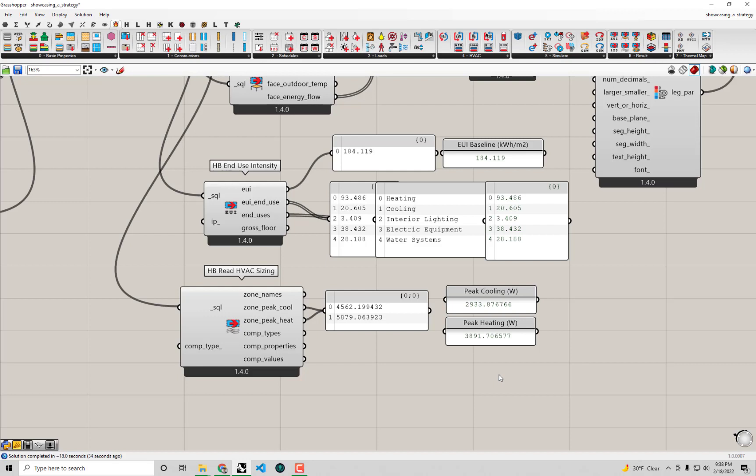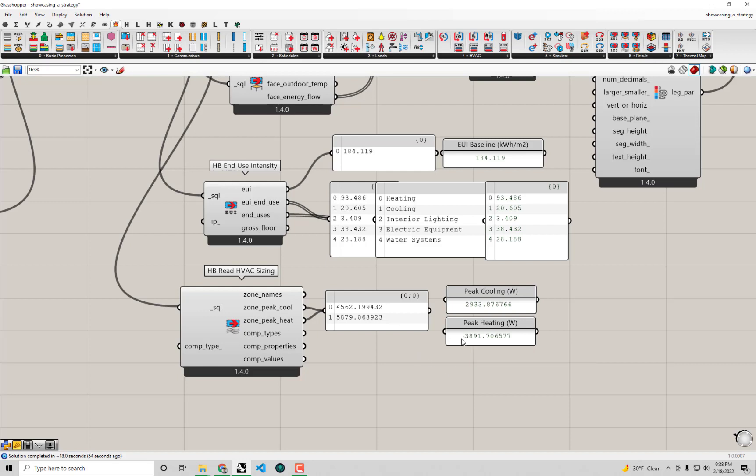This could be pretty significant. It may not be a direct one-to-one savings in terms of the percentage reduction in the cost of the system, but I'm pretty sure we can step down at least one size of a cooling system if we were to implement an energy retrofit like this. Similarly, the heating is not quite halved but it's at least two-thirds of what it would have been otherwise. We could look into the actual costs of different sizes of systems to really evaluate this, but this at least gives us a rough idea of how much we could save using a strategy like this.